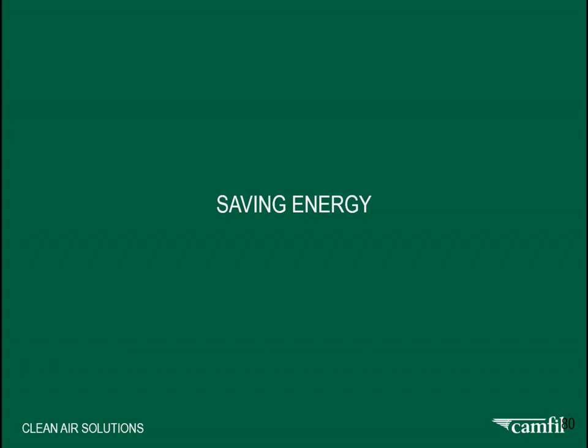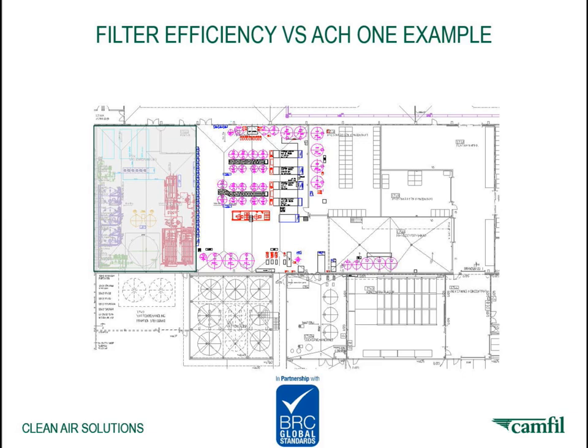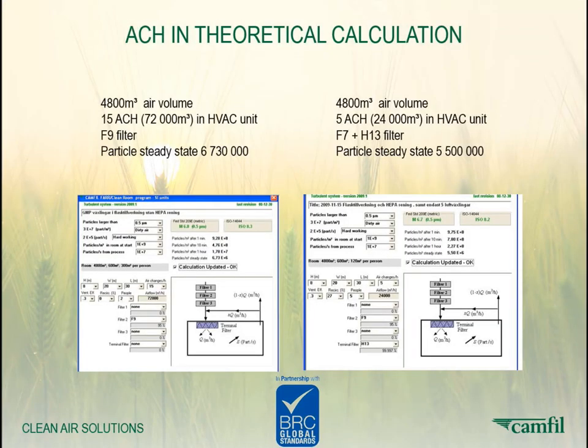And now we should look at some potential in saving energy. Filter efficiency versus air changes, one example. If you look at the gray zone, the analyzed area, which has 4,800 cubic meters of air. The existing solution had F9 filters in the existing HVAC unit with 15 air changes. In the examples, we see a theoretical calculation of this, but with different air changes. To the left, you see 15 air changes, equal to 72,000 cubic meters through an HVAC unit with F9 filter. In our clean room program, we calculate the particle steady state of 6.7 million.